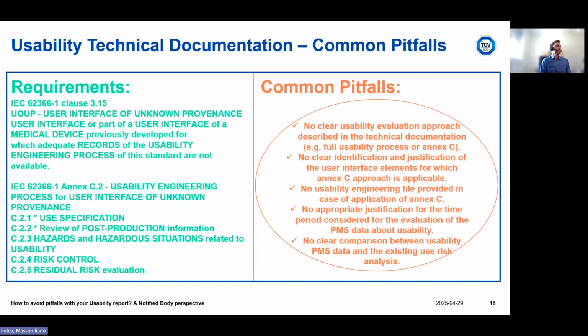Then the manufacturer has to evaluate the available product risk analysis, checking that all the risks, hazards, and hazardous situations related to usability have already been identified in the risk analysis, comparing what is inside the risk analysis with the post-market surveillance data, the post-production information of step 2. So, comparing the product risk analysis with the information coming from the field in the chosen period of time.